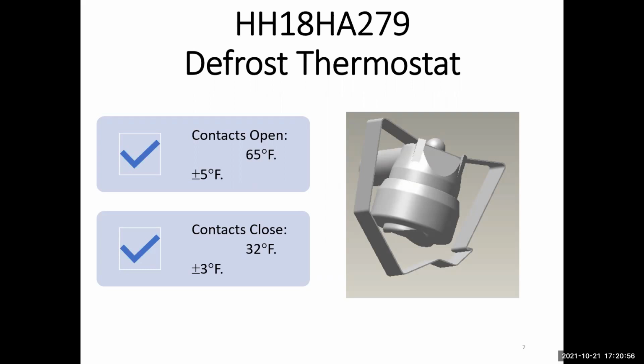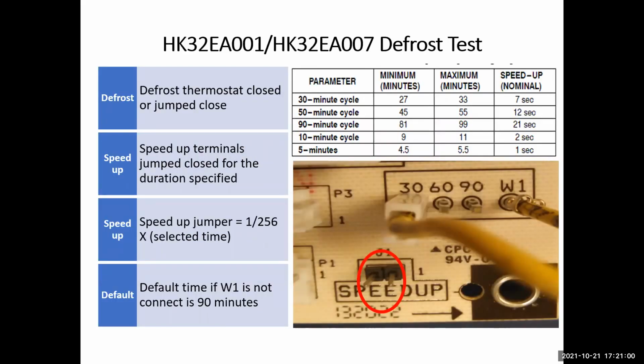So what we're saying there is, we look up at the chart and we've got 30, 60, and 90. When we have that particular one, it's letting you know that we're going to have compressor heating going on until the thermostat closes. When the thermostat closes, now the timer begins. On this particular one, we have a 30-minute setting, so it's still going to run on compressor heat for 30 minutes. During that time, as long as the defrost thermostat does not open, it will initiate your defrost.